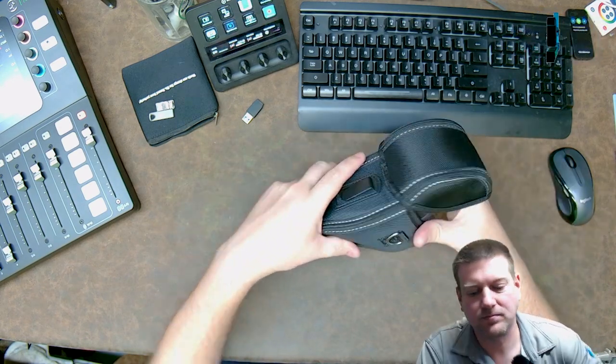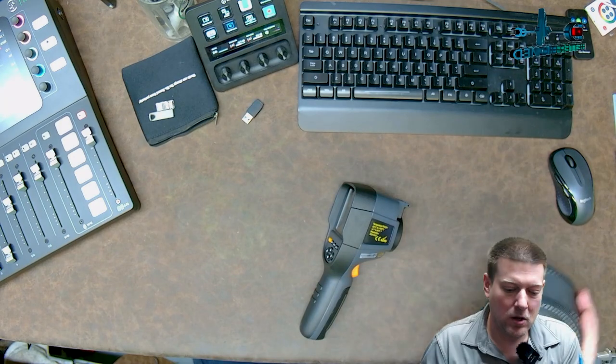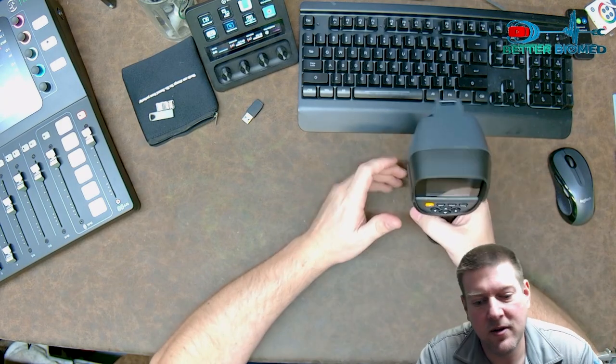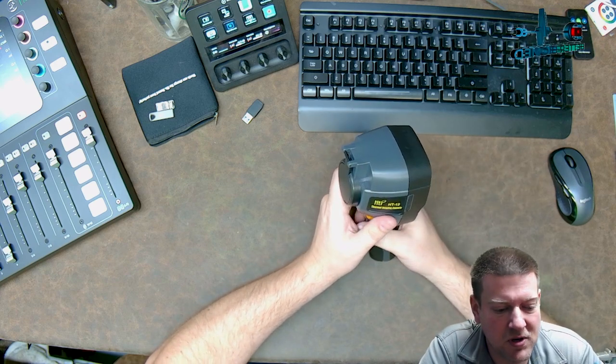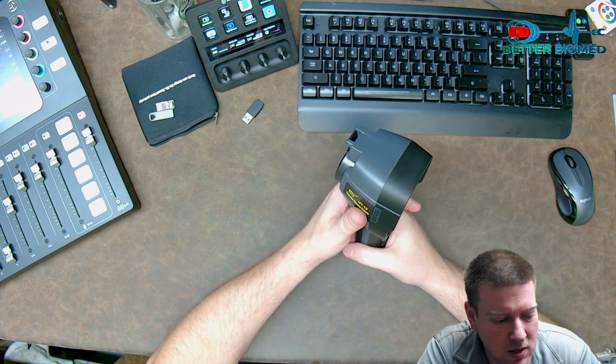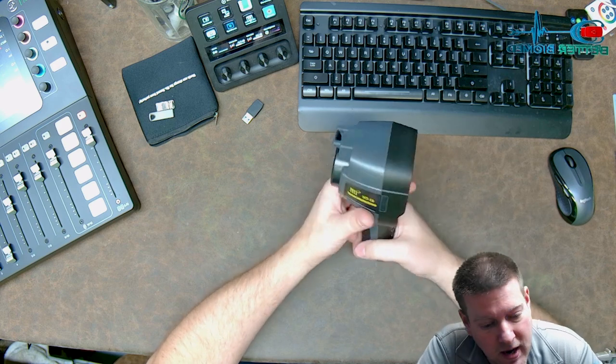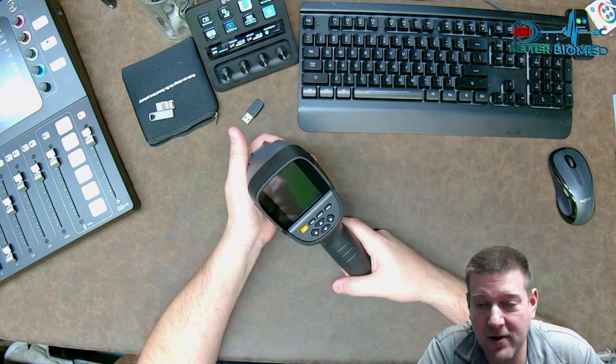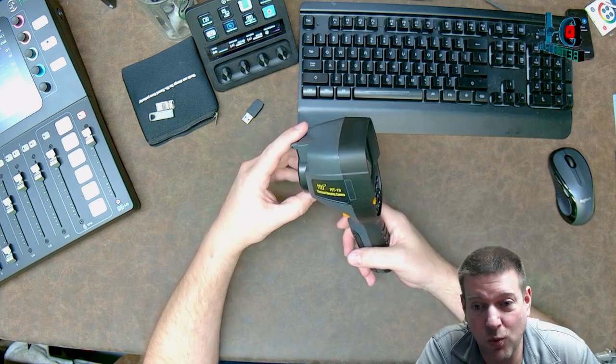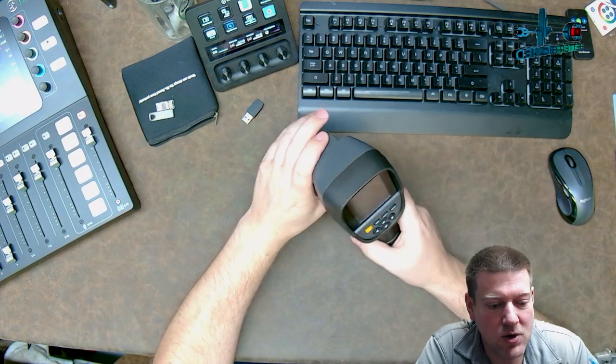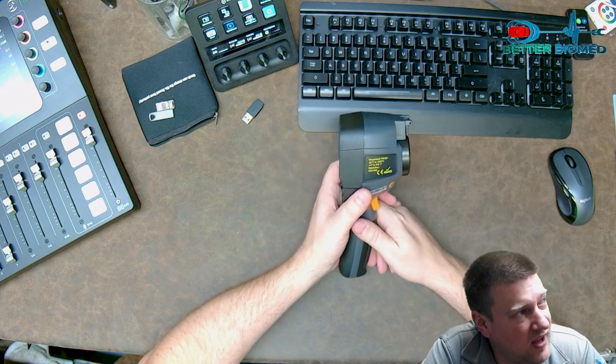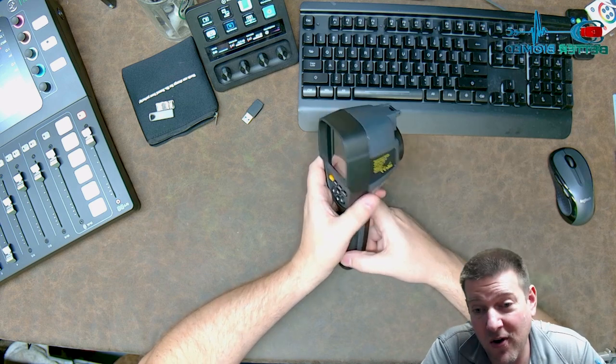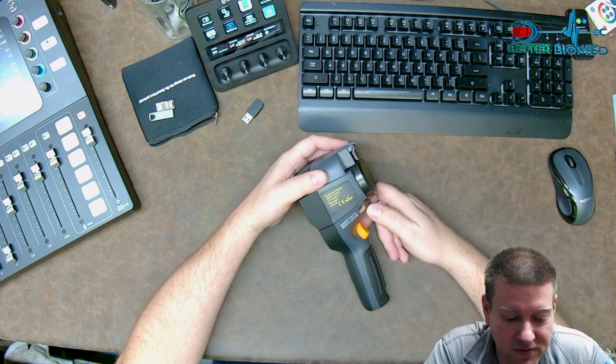So let's go ahead and take a look. Now there's some things that you should know about infrared cameras. It is in fact a camera, but it's a camera that captures the infrared spectrum. And there is a spectrum there. So certain objects give off infrared. Everything technically gives off infrared. And that's because everything has different levels of heat. And that's what your camera does is your camera just analyzes the amount of infrared emitting or bouncing off of objects. So some objects like shiny objects are going to look like they're white hot, but that's because the infrared that it's sending out is being reflected back.